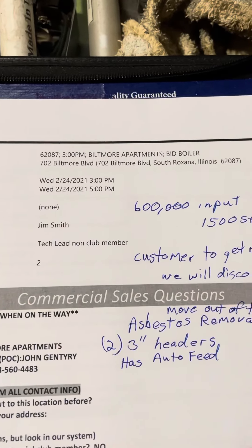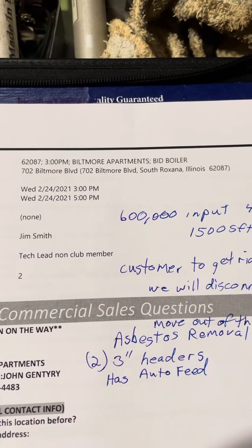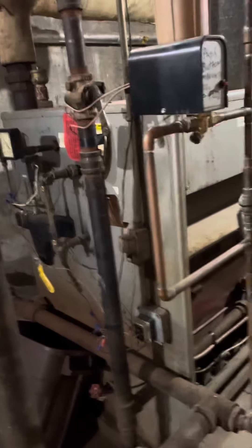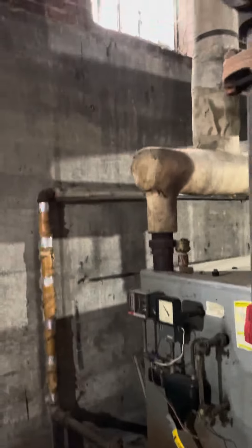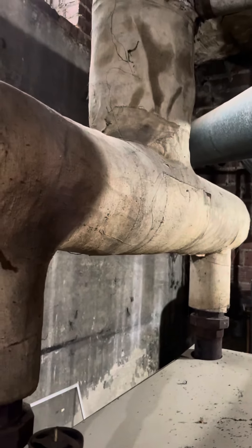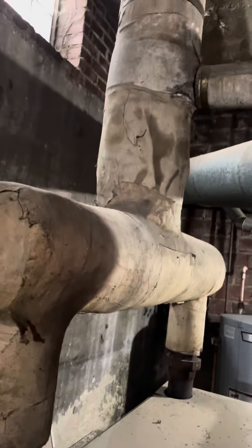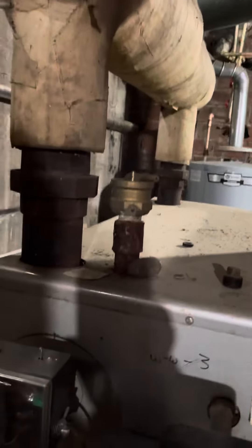We are at Biltmore Apartments, South Roxana, Illinois. We have a 600,000 BTU input steam boiler, natural draft. We do not have a Hartford loop to start with. We have two three-inch risers going into one asbestos-covered main riser, or main header.